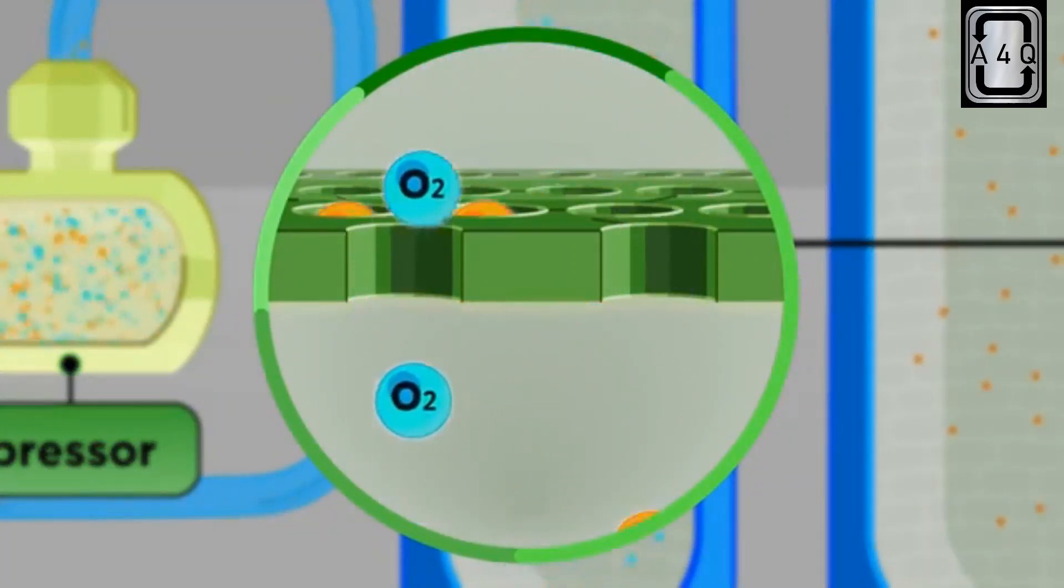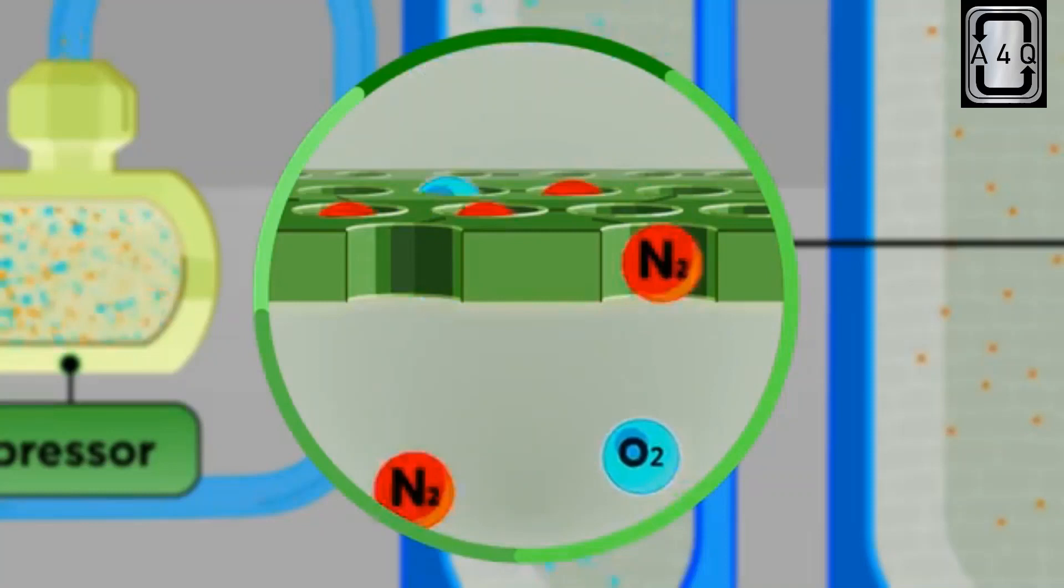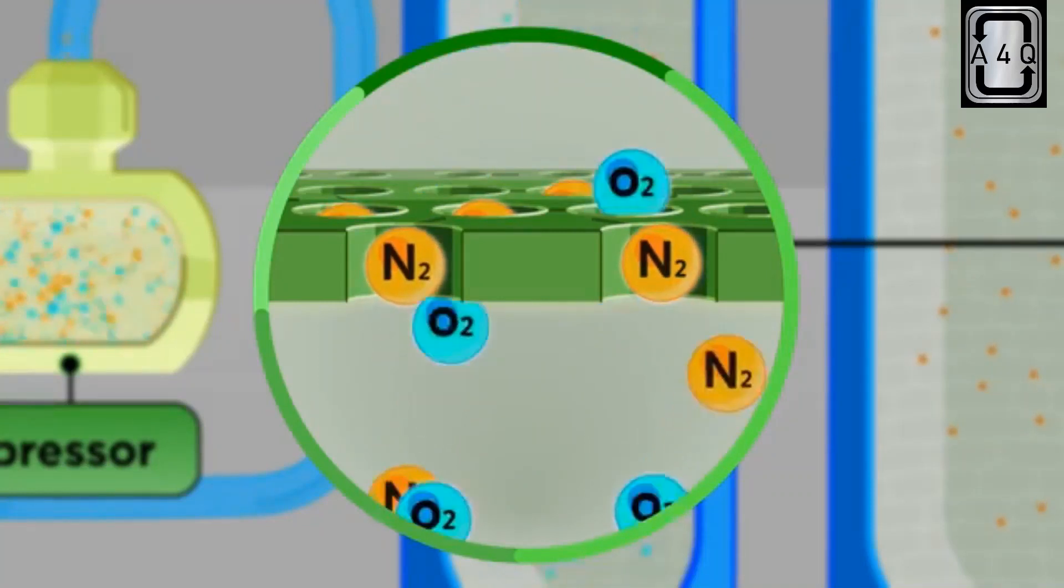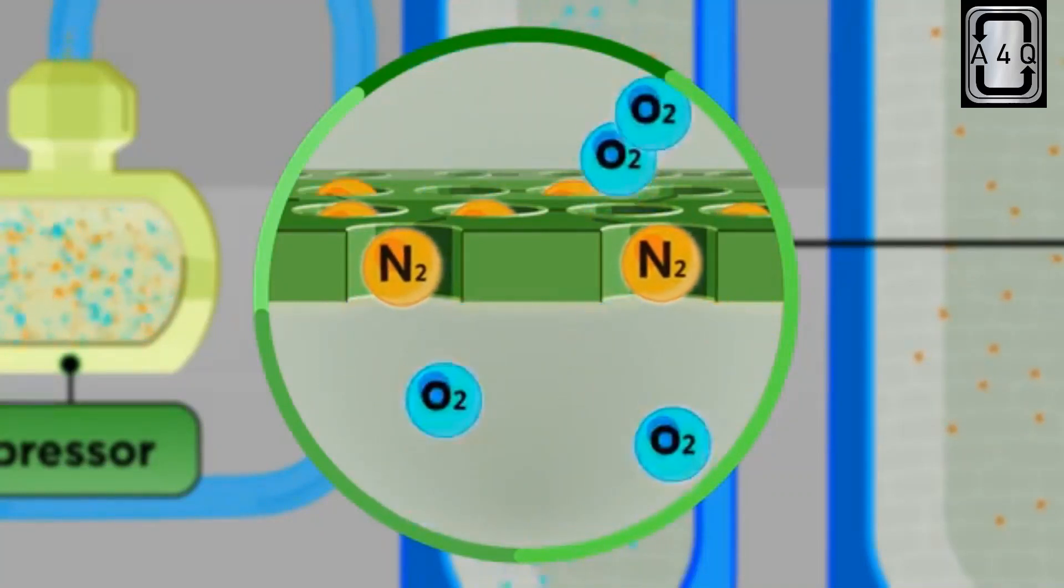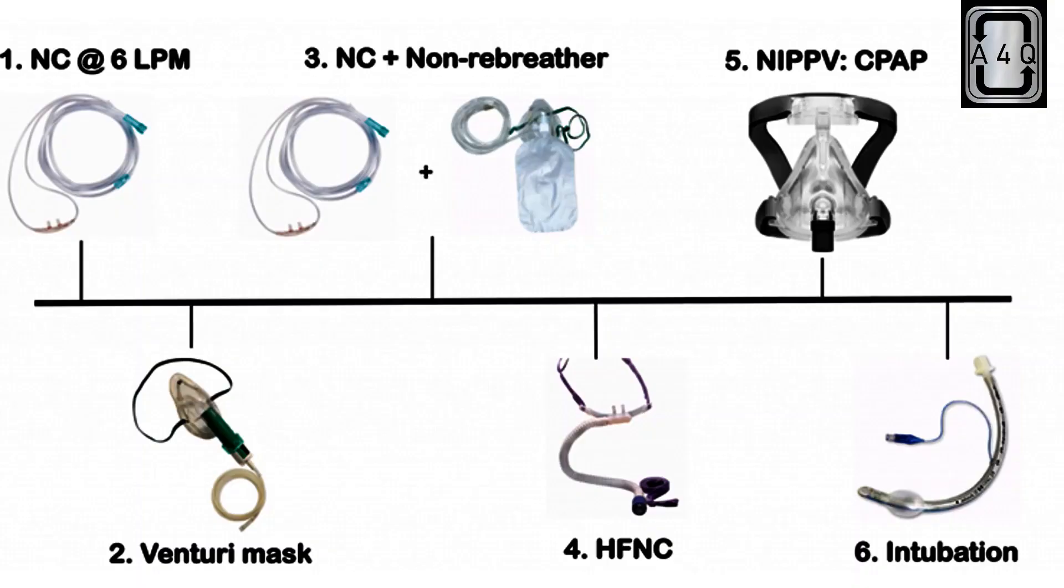So what comes out of the tank is 90 to 95% pure oxygen ready to be supplied to the patient via an oxygen delivery system like nasal cannula, oxygen mask, etc.